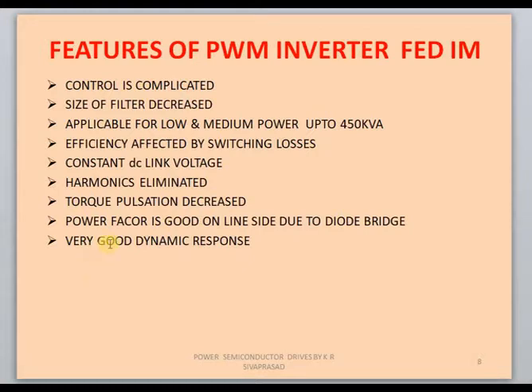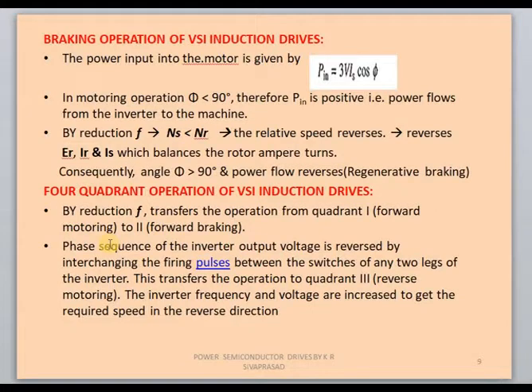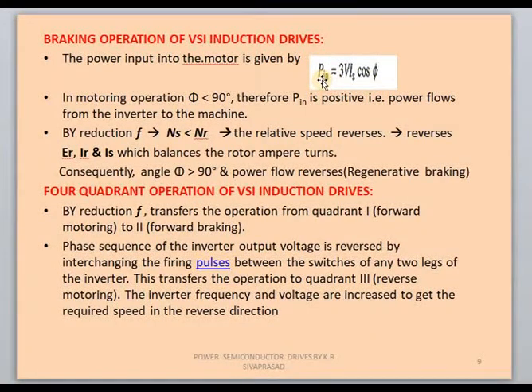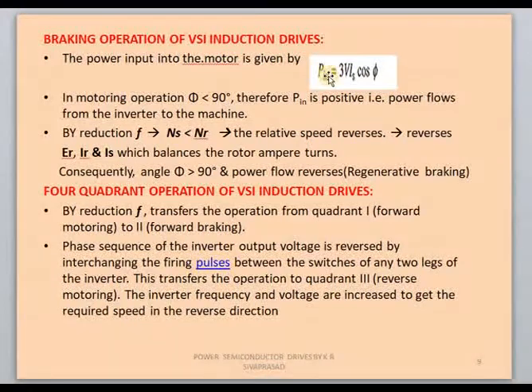It produces very good dynamic and transient responses. Now we move on to braking operation and four-quadrant operation of VSI. For the braking operation, the power input to the motor is P_in = 3 × V_phase × I_phase × cos(φ). When power is positive, power transfers from inverter to the machine — this is motoring mode, where φ should be less than 90 degrees. To operate in braking or regenerating mode, the power flow is opposite to motoring.